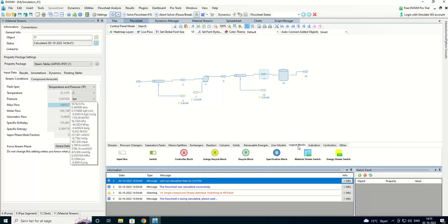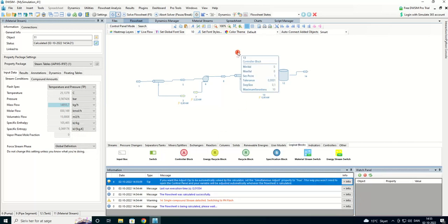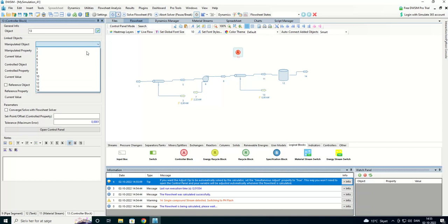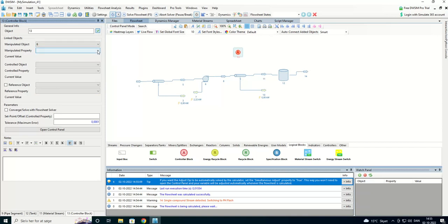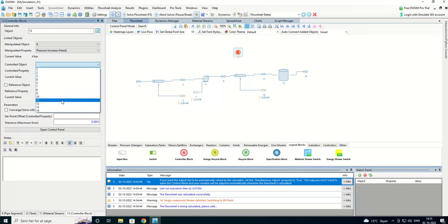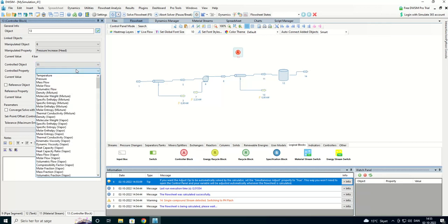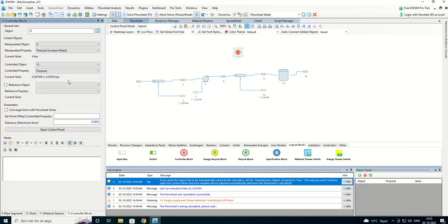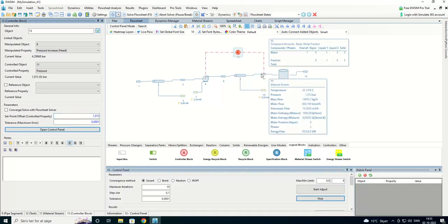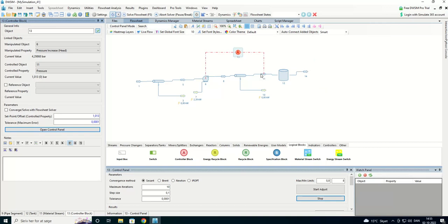I'm going to add a logical block. Controller block. That's just the easy way. So I don't have to adjust it by myself. The manipulated object is the pump. It has number six here. And it's the pressure head. The four bars here. The control object is the flow stream 11. And it's the pressure we want to adjust. And that is 1.013 equal to one bar. Let's look how that's going to be.